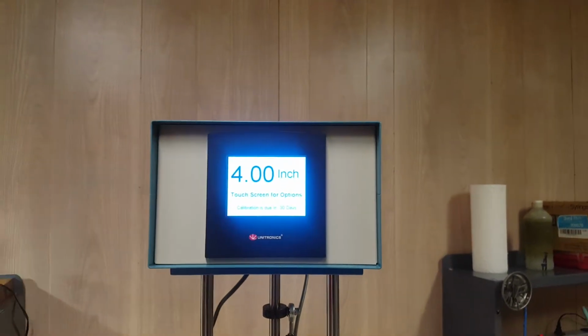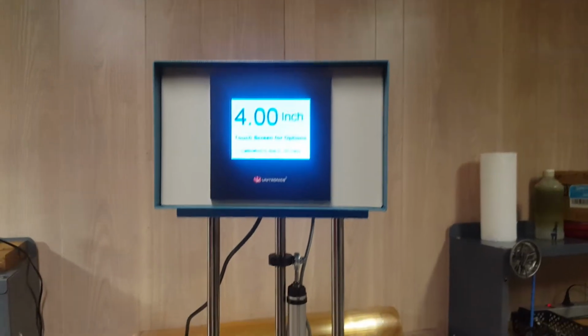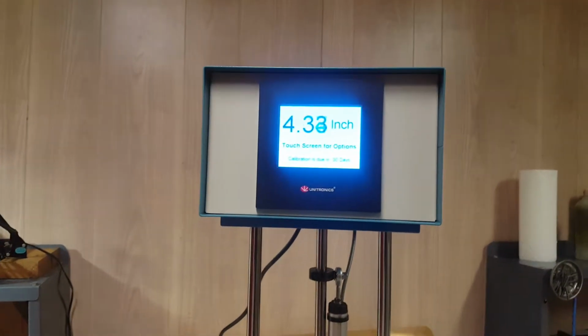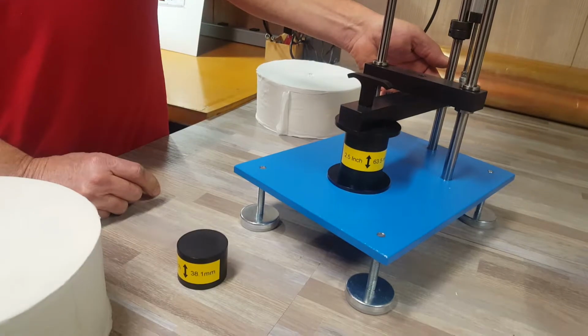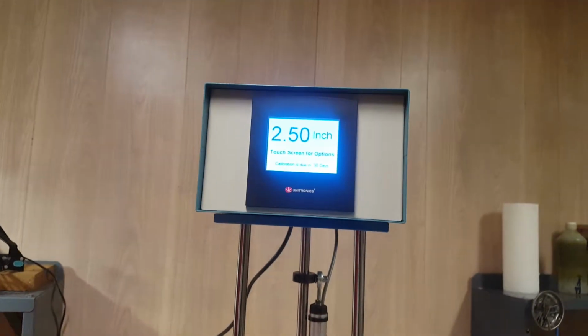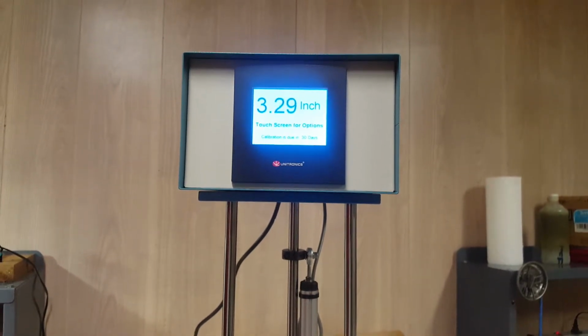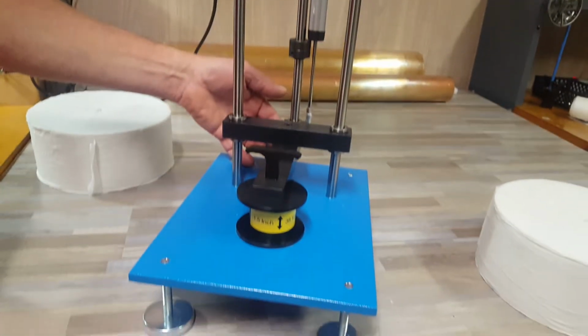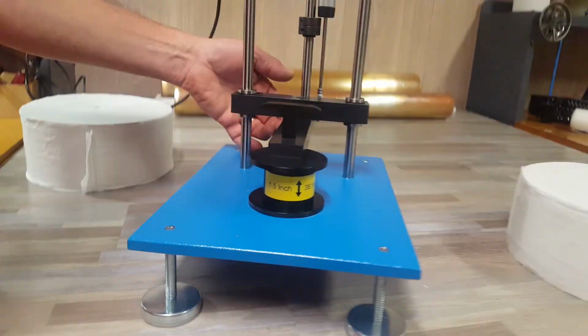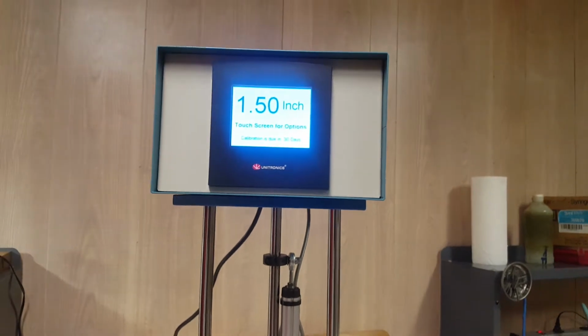If I go back to our display, we see that we have the 4-inch gauge blocks in, and we measure 4 inches. If I take the 1.5 out and have the 2.5 remain, we look at the display and we see that it reads 2.5 inches, so it verifies that it's reading correctly. And if I take the 2.5 out and I put the 1.5 in, we see that it measures 1.5 on the display, which verifies that it's calibrated correctly.